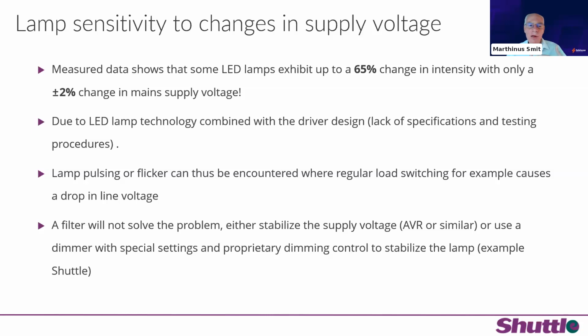The resolution of this problem is rather difficult. We see that this problem is now not only limited to filament LED lamps, it's spilling over into GU10s and A60s and so on, as the driver design used in the filament lamps is adopted into your smaller lamps as well. So unfortunately, a filter will not solve that problem, because a filter can typically not filter out such a big difference in your mains supply voltage.